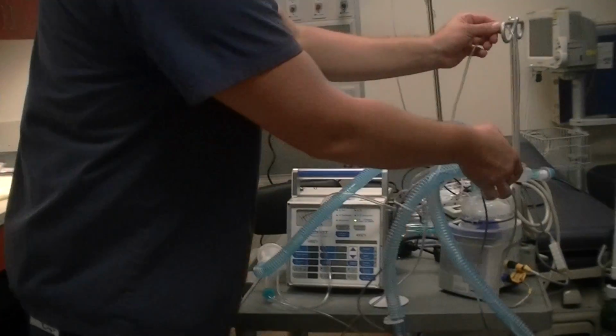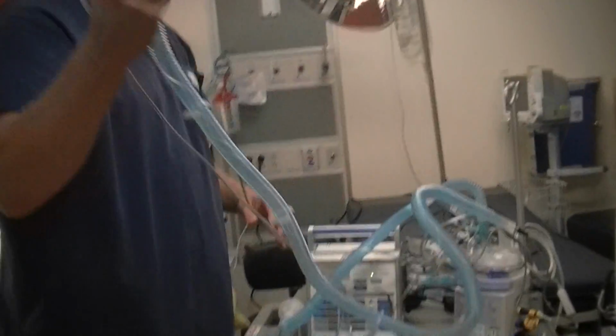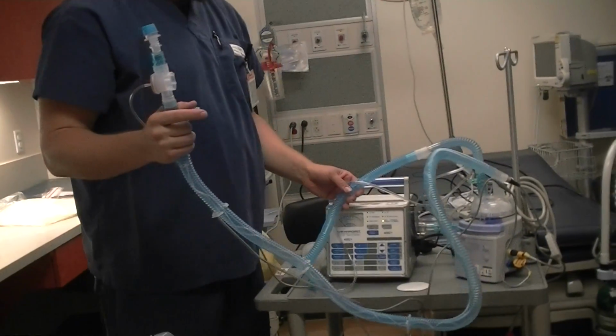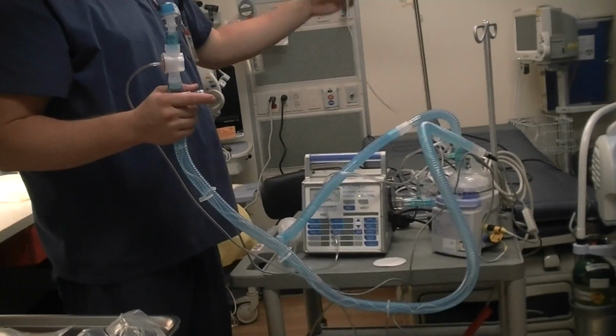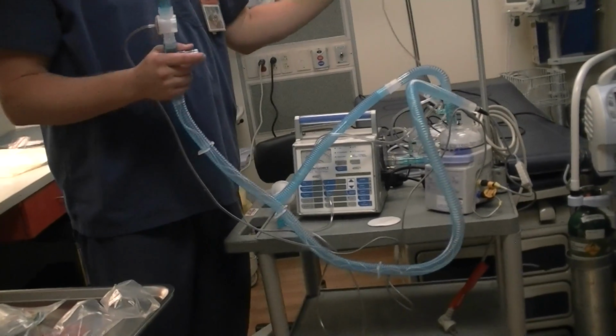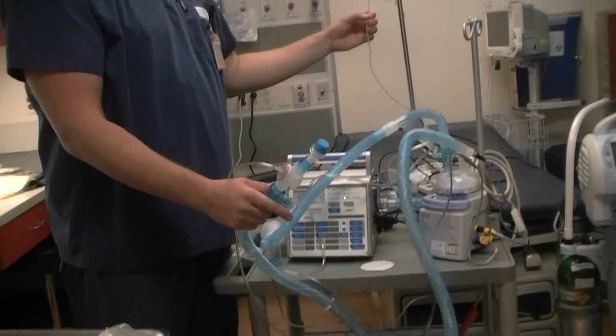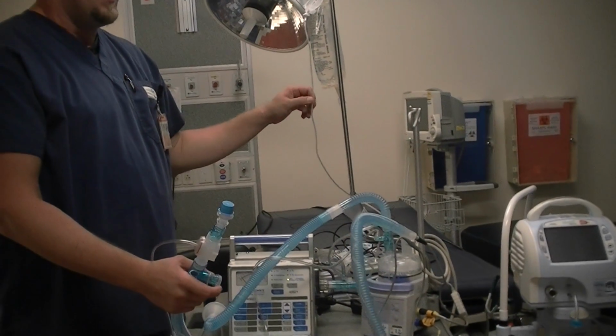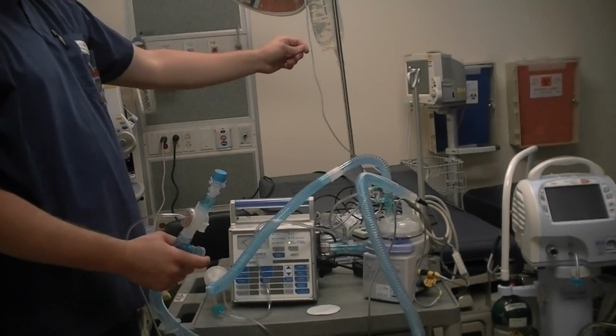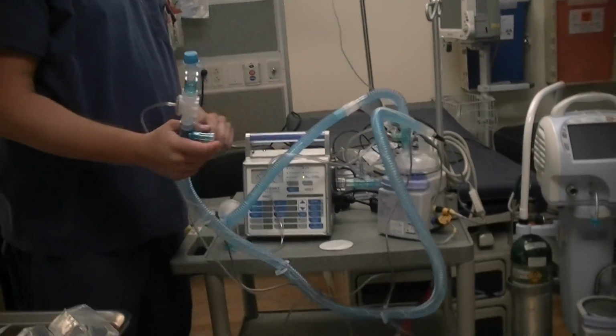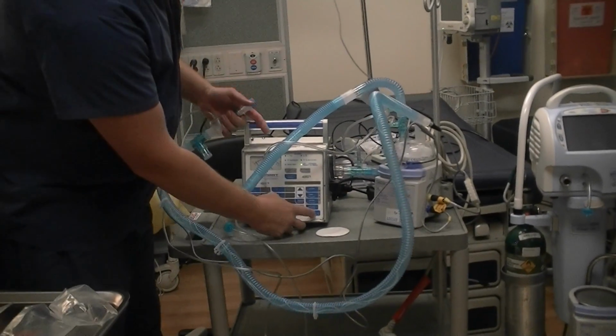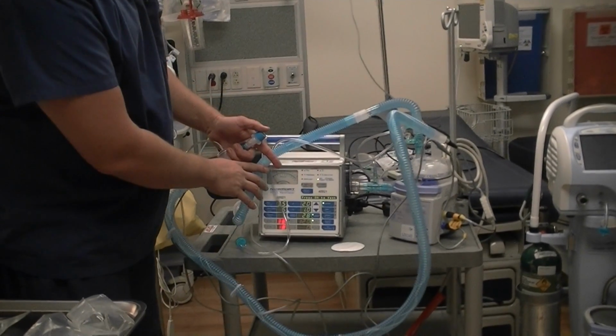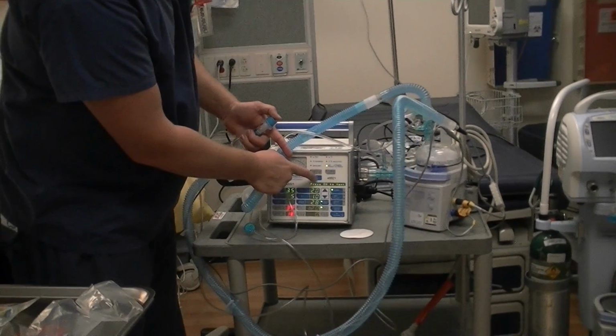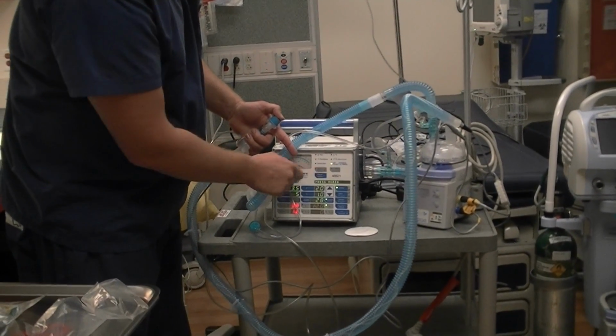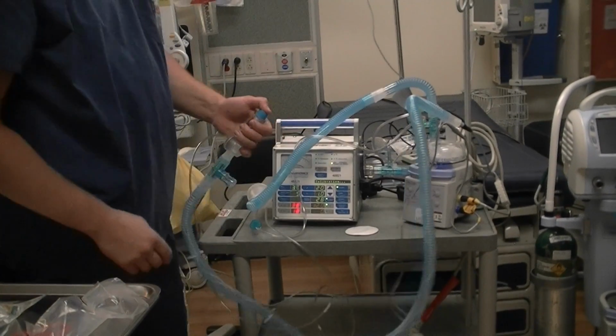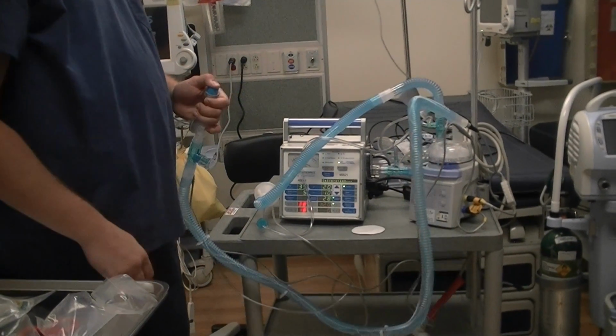Okay? So our circuit now is basically set up. We're going to run the cal test. If you have to, go ahead and pinch the water off with some clamps if you want, or just don't poke your water until after the cal is done. So we're going to turn on our ventilator, and you're going to press the manual inflation button. It says press again. And now it's going to run its calibration.